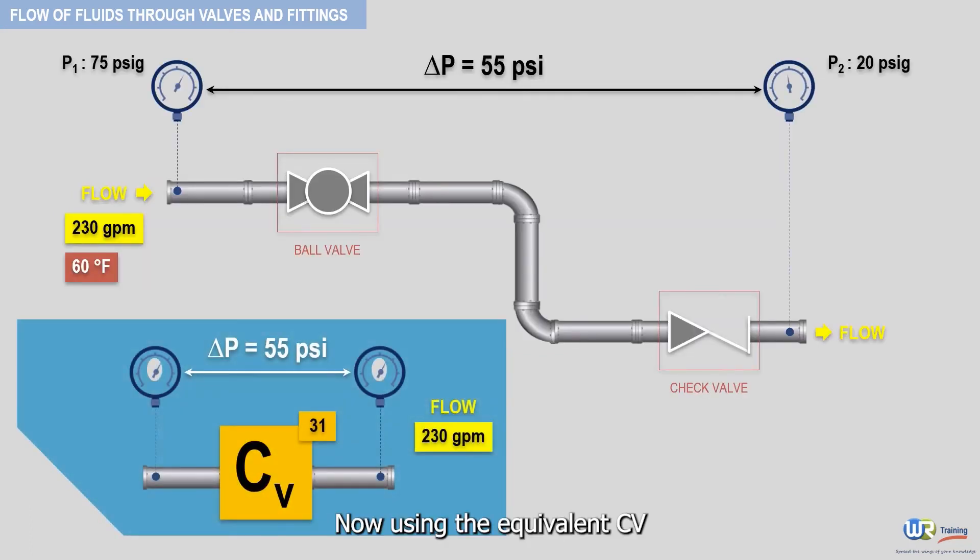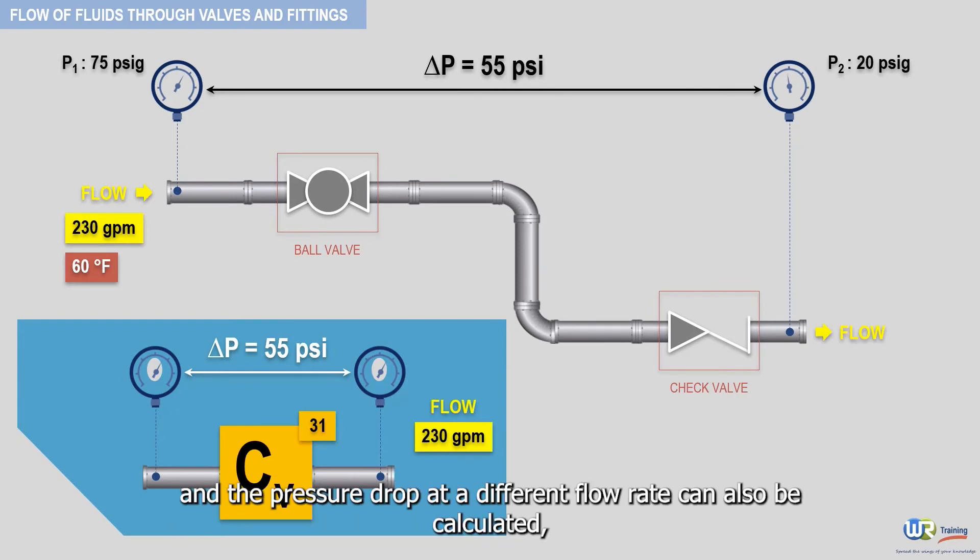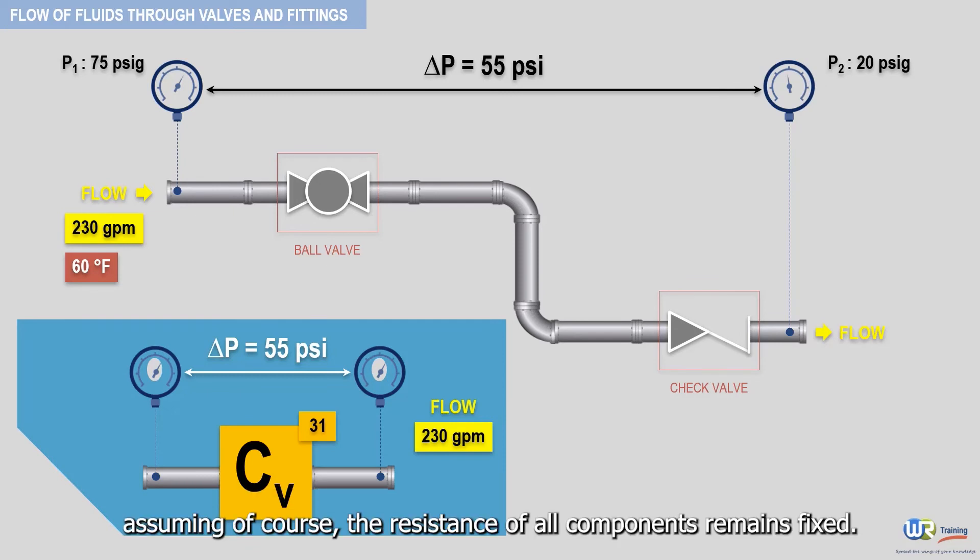Now, using the equivalent CV, the flow rate at a different pressure drop can be calculated, and the pressure drop at a different flow rate can also be calculated, assuming of course the resistance of all components remains fixed.